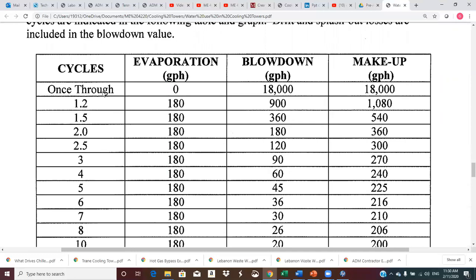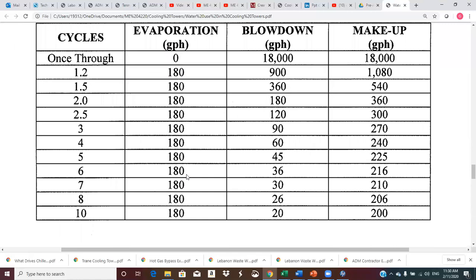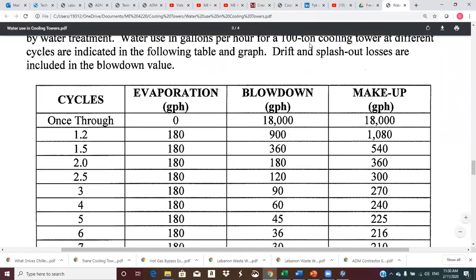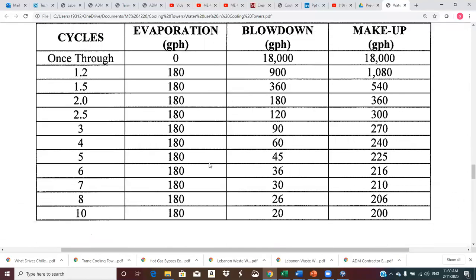So everything comes in, everything goes out. And so we're showing 18,000 gallons per hour. So if we're running 1.2 cycles of concentration, then the evaporation is 180. The evaporation is going to be the same for the same 100 tons of cooling capacity, because it's 1.8 per ton. So 1.8 times 100 is 180. Then the blowdown at 1.2 cycles is 900, and the 900 plus 180 is 1080.